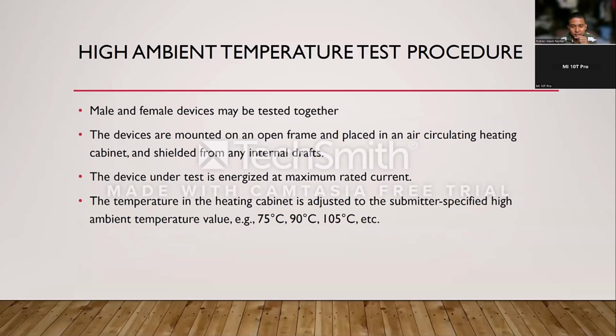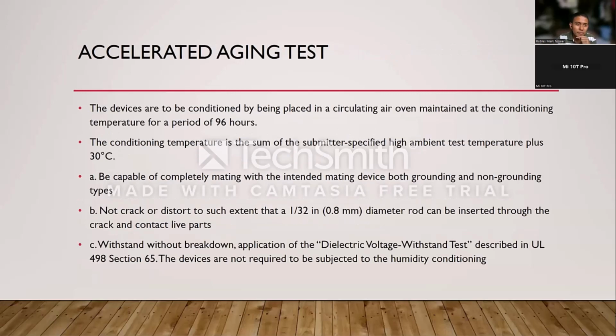Temperature in the heating cabinet is adjusted. Ayan, kailangan may temperature na required. About 75 degrees Celsius, 90 degrees to 105 degrees Celsius. Accelerated aging test. The devices are to be conditioned by being placed in circulating conditioning temperature for a period of 96 hours.